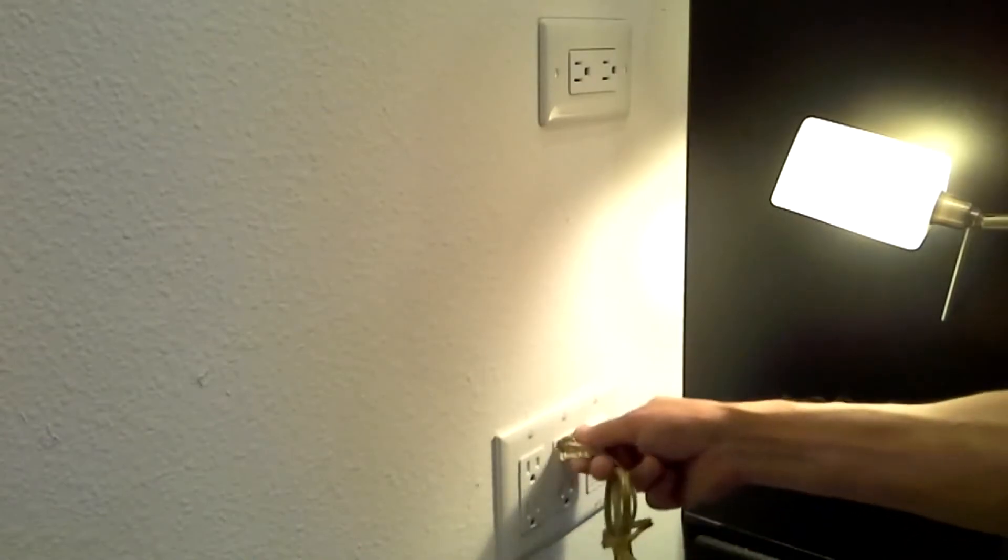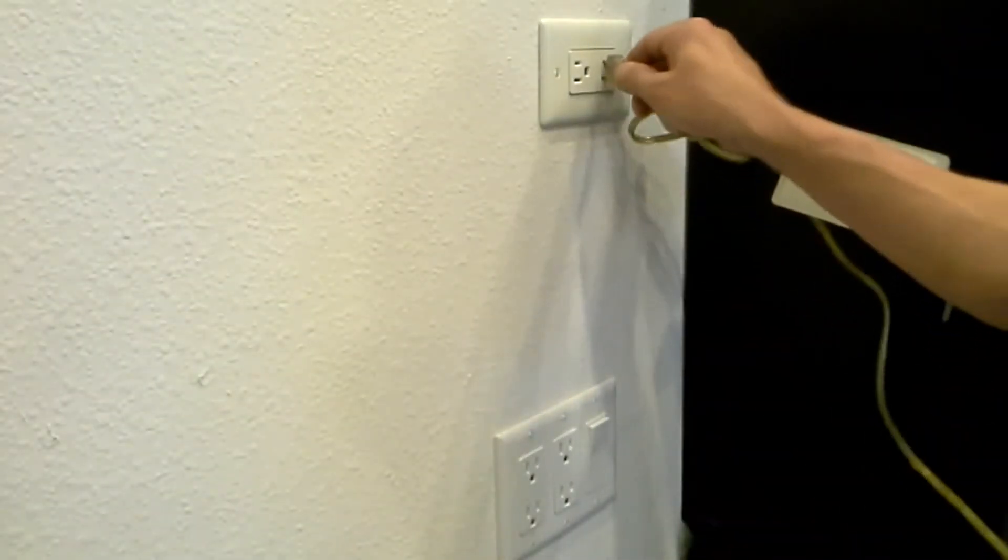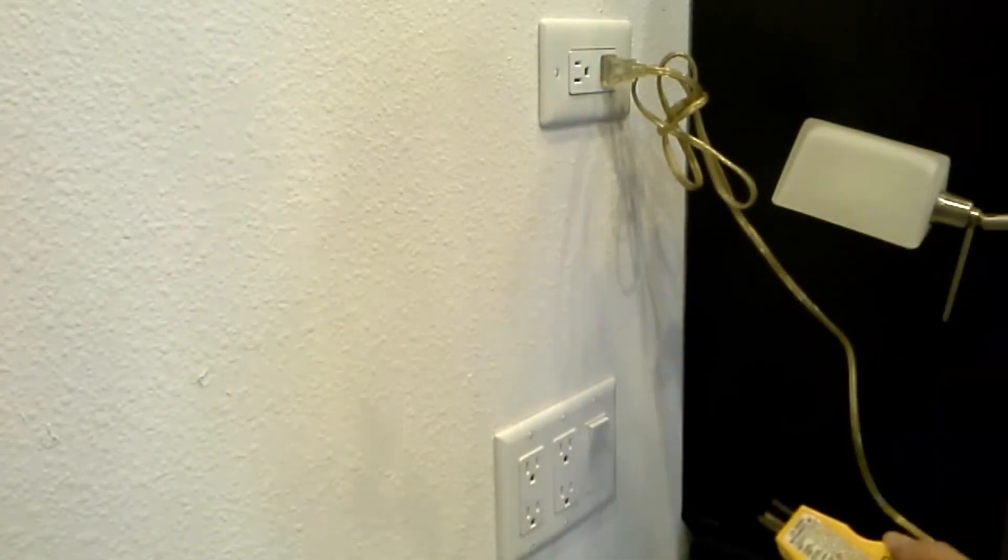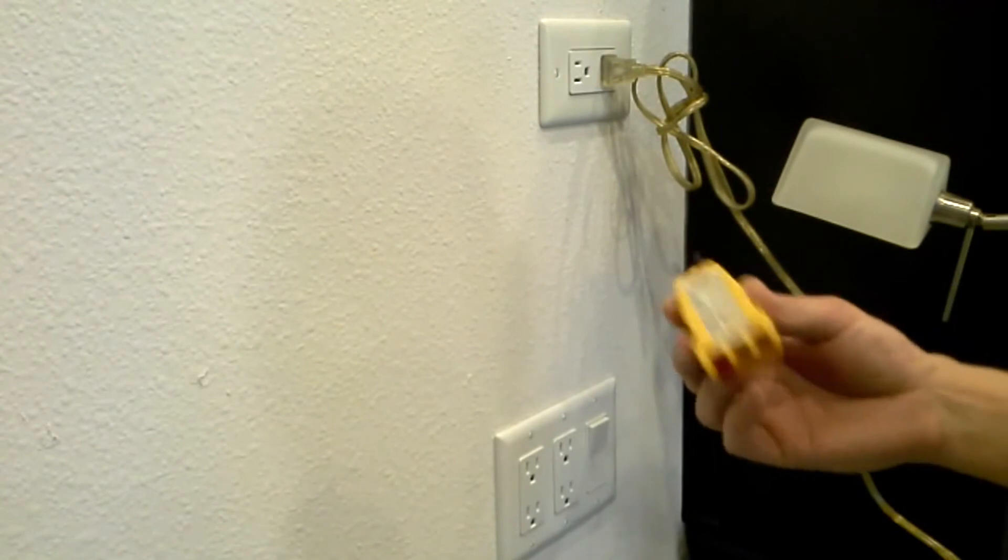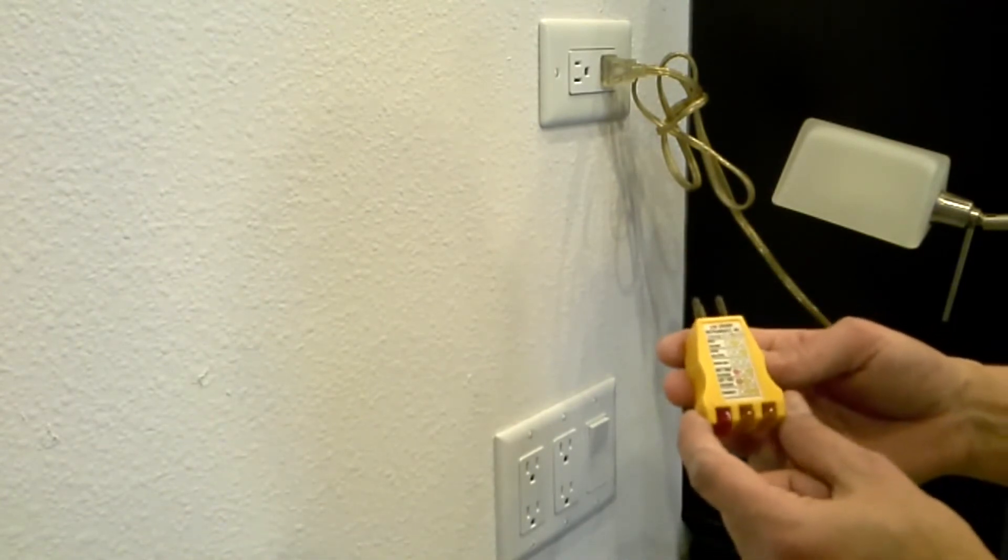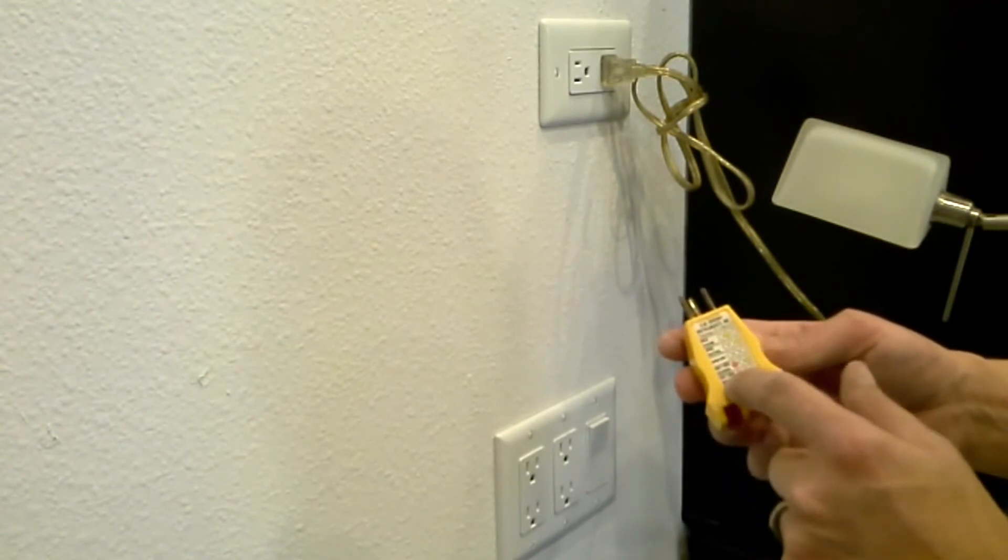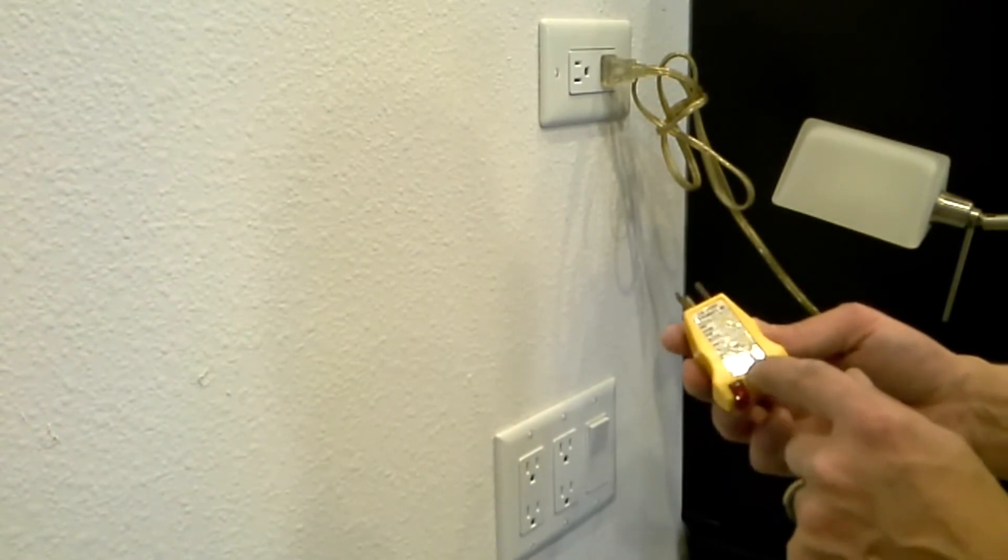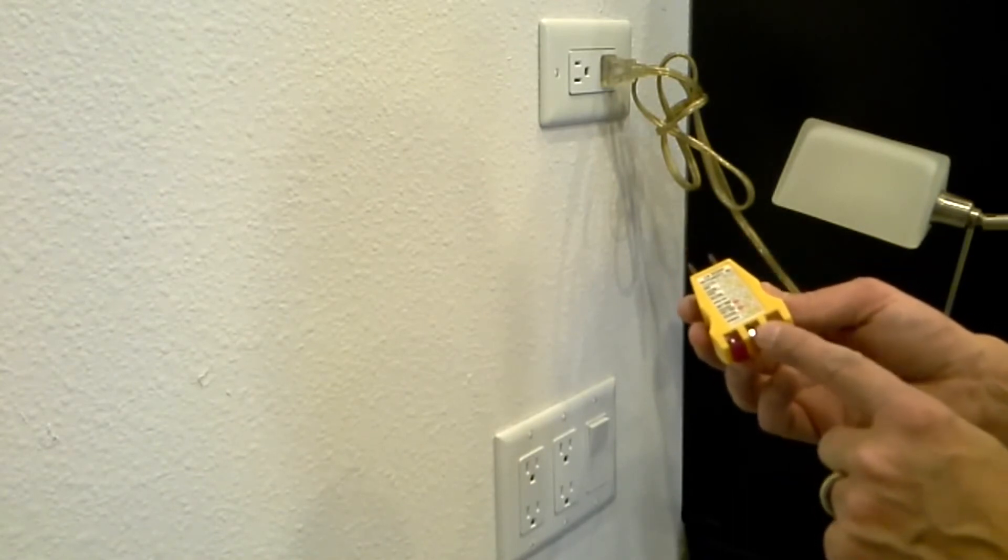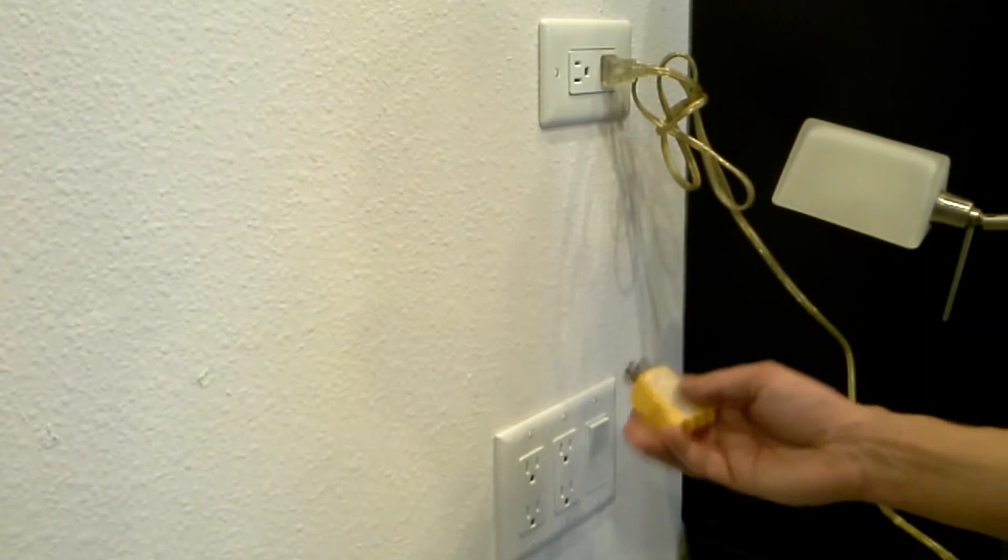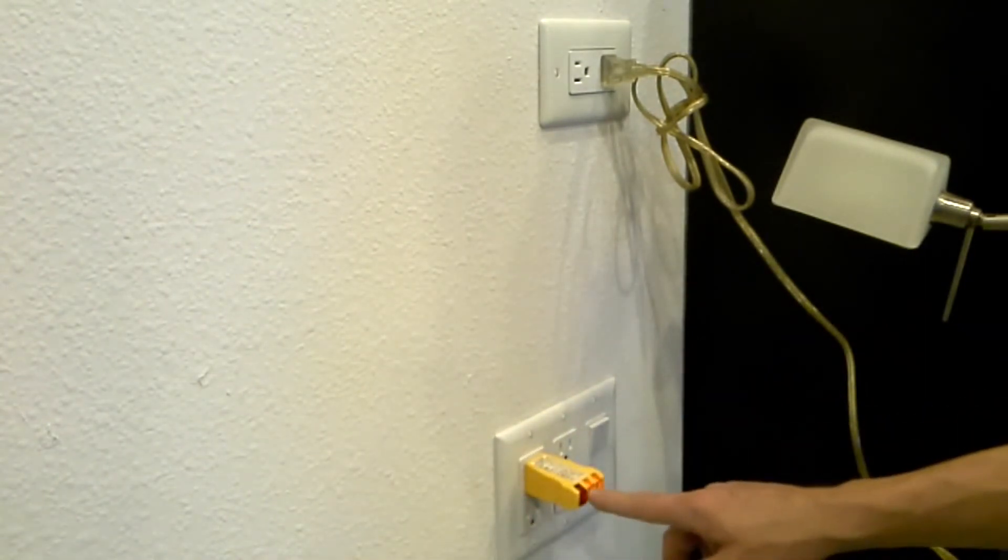One other thing you can use after you've done your electrical installing outlets is this handy tester. You can pick these up for a few bucks at Home Depot or Lowe's. It tells you the different problems you may have depending on the lights that come on here. What you want for correct is for these two amber lights to come on and no red light. Test this here, we've got correct. Wired correctly.